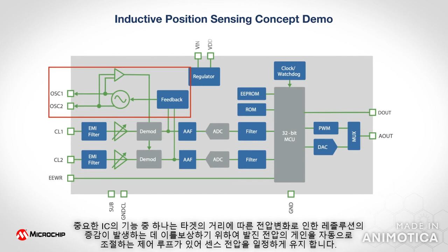To preserve resolution, in the chip design we implement an air gap compensation method using an automatic gain control loop. As we change the air gap to a higher value, we dynamically compensate the excitation voltage, maintaining a maximum voltage swing for both analog channels to preserve the resolution we use to calculate position - which is very important for many potential applications.